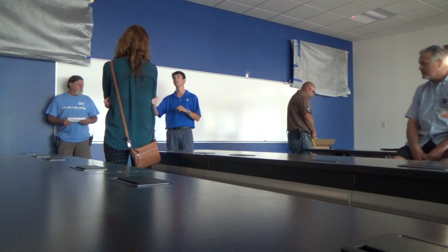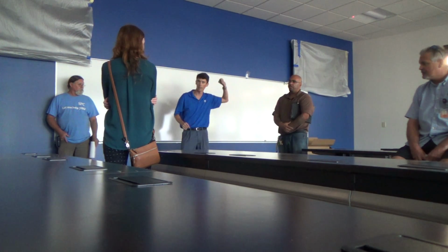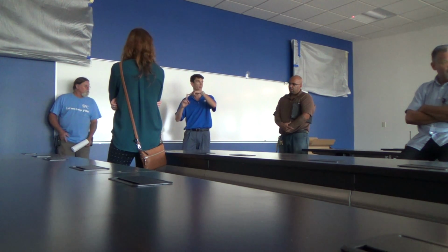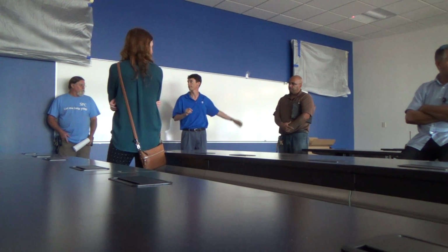Right, so like we were saying, all these devices that we're talking about, the switches, the ceiling sensors, and the power packs are connected with Cat5, and that daisy chain, is what we call it, goes back to the hub that goes back to the gateway or the brain. So we can see all these devices from the gateway, but we can do that because they're all connected with Cat5. So you'll notice on every InLight device, which is the brand of lighting controls here, there'll be 2 Cat5 ports. In every room, there's going to be a dead end with one device that just has one piece of Cat5 coming to it, and then the other end of that makes it back to the hub that eventually goes back to the brain.